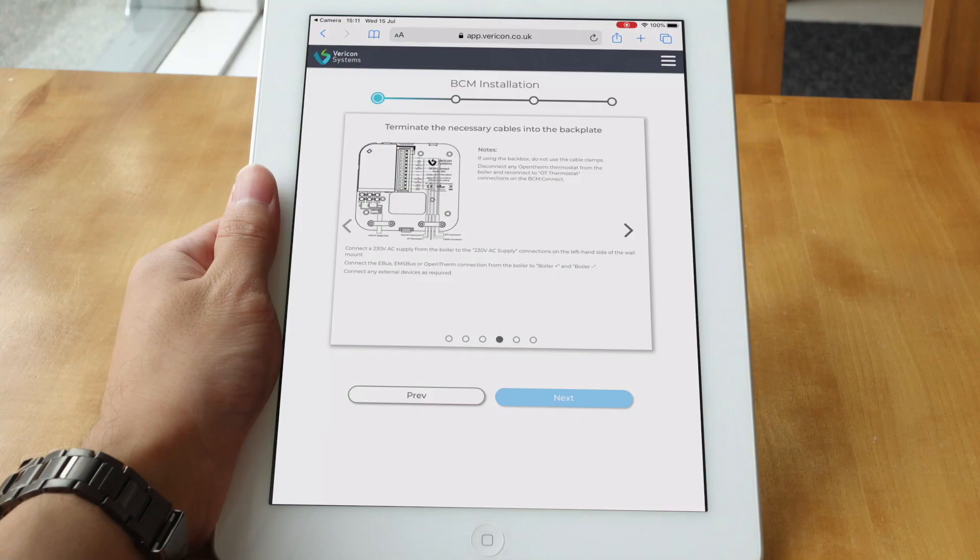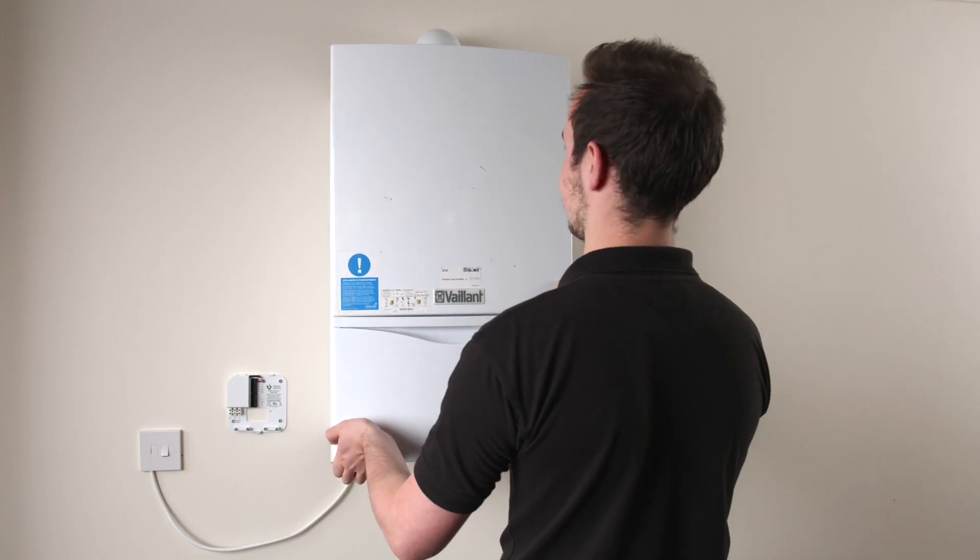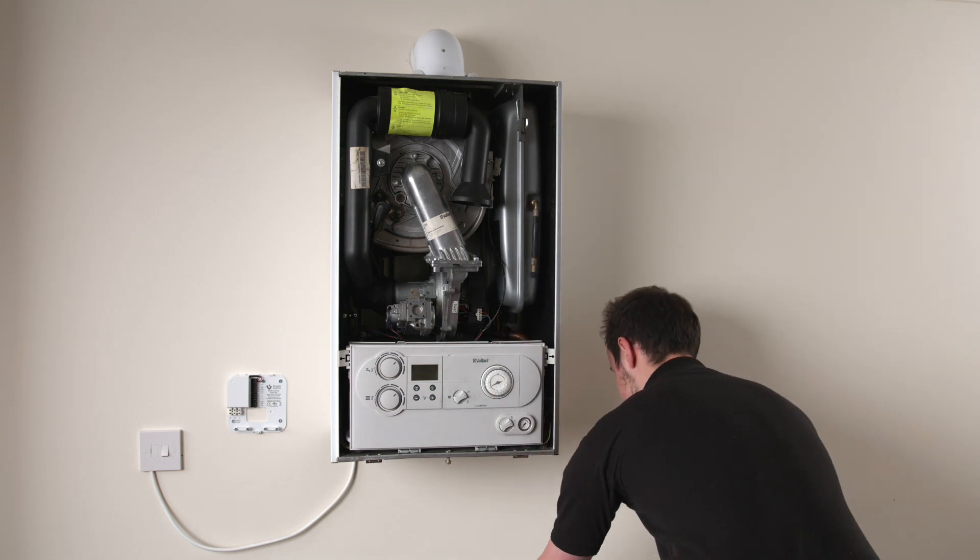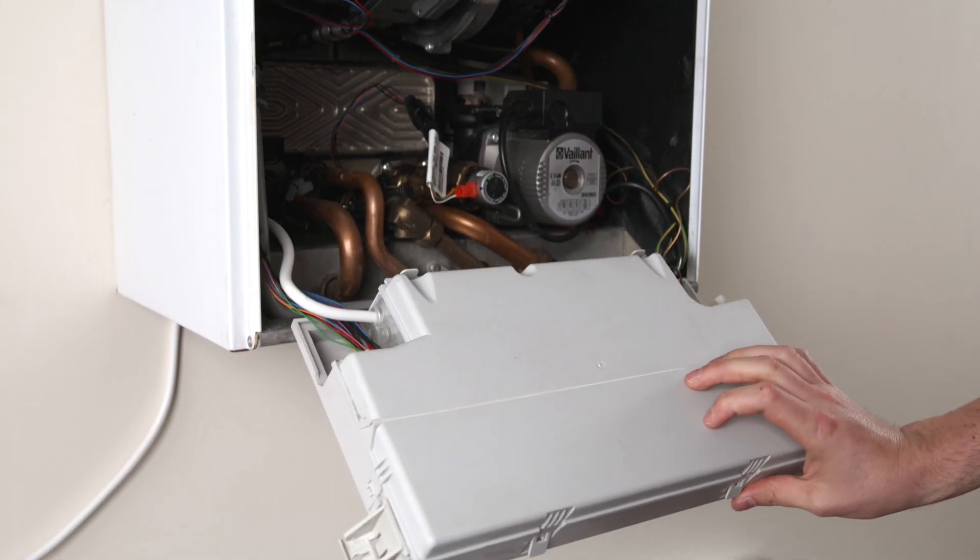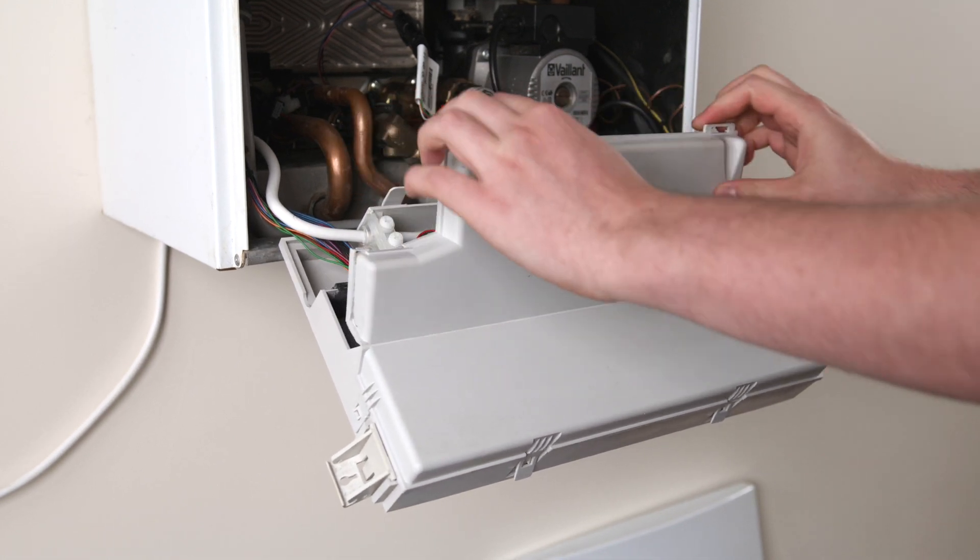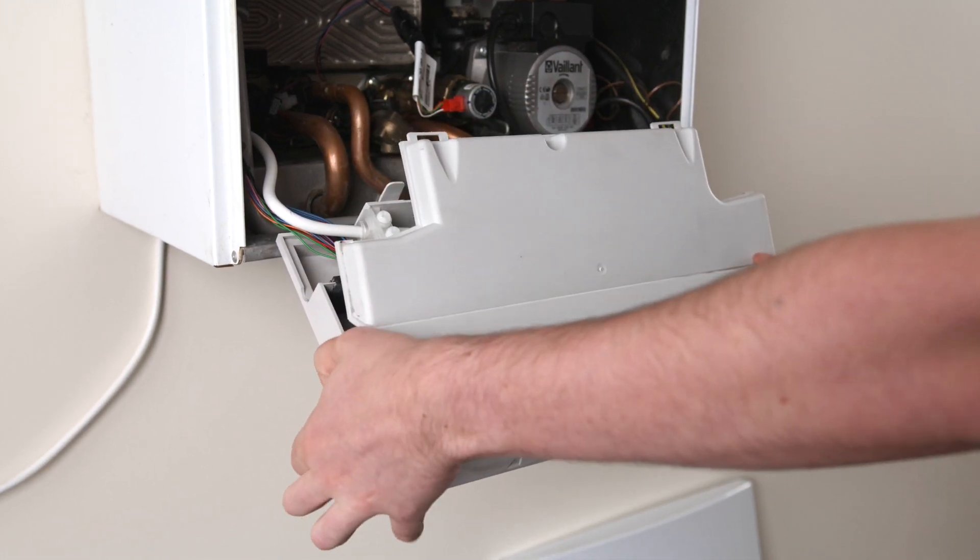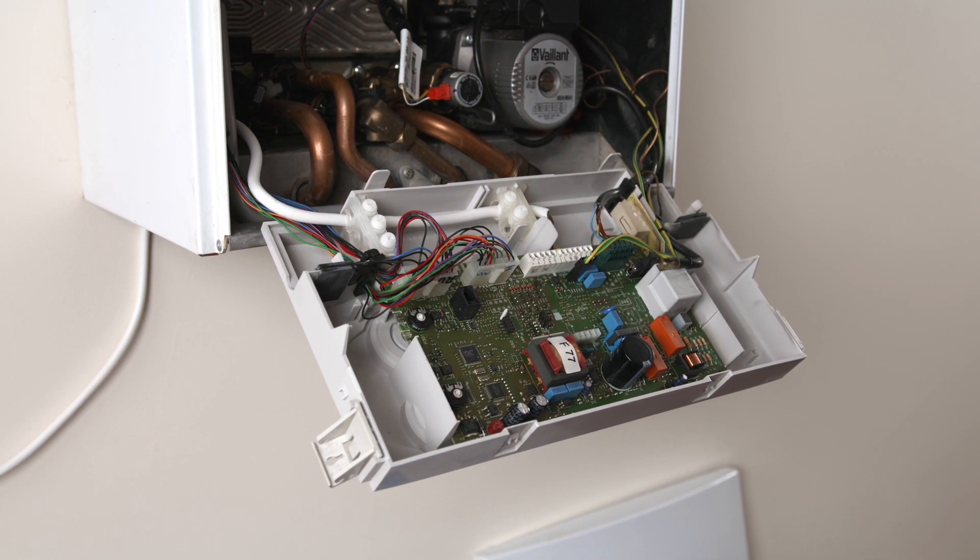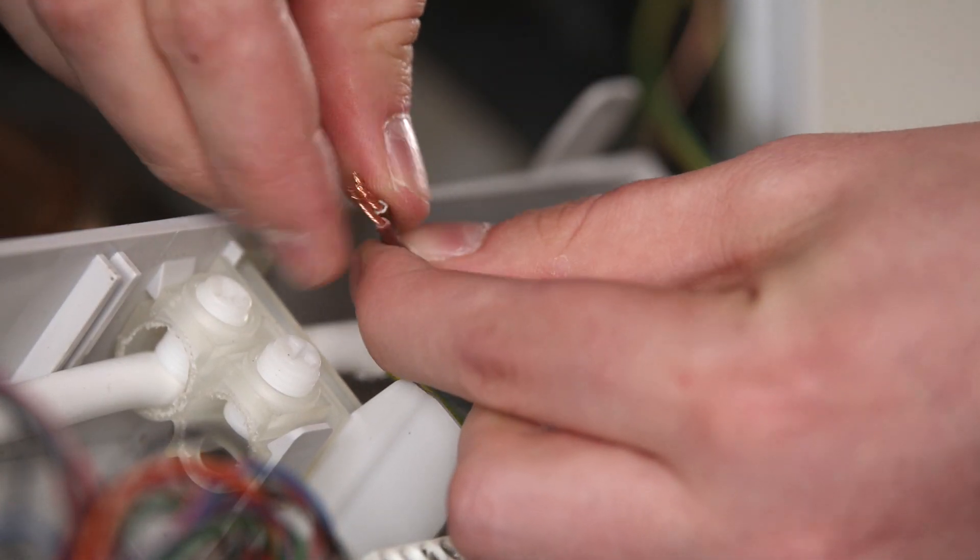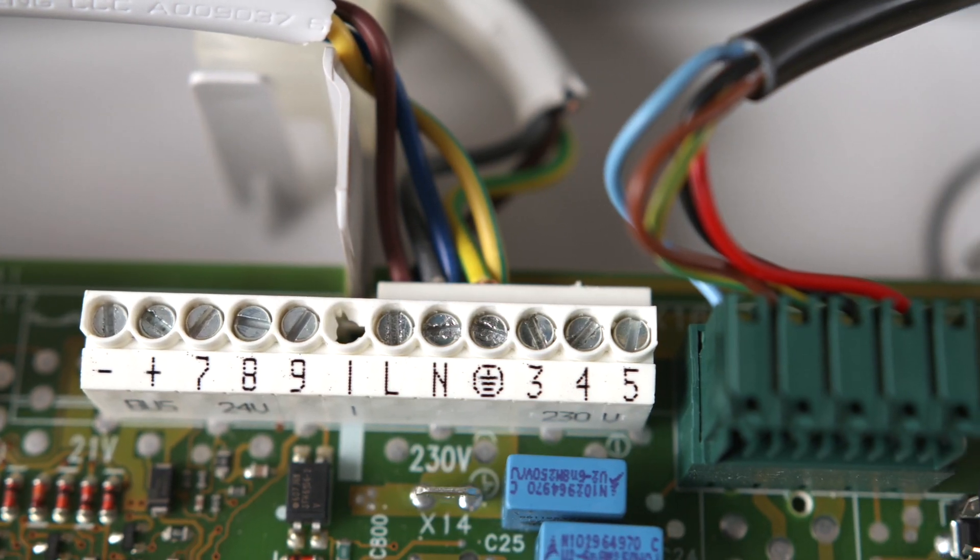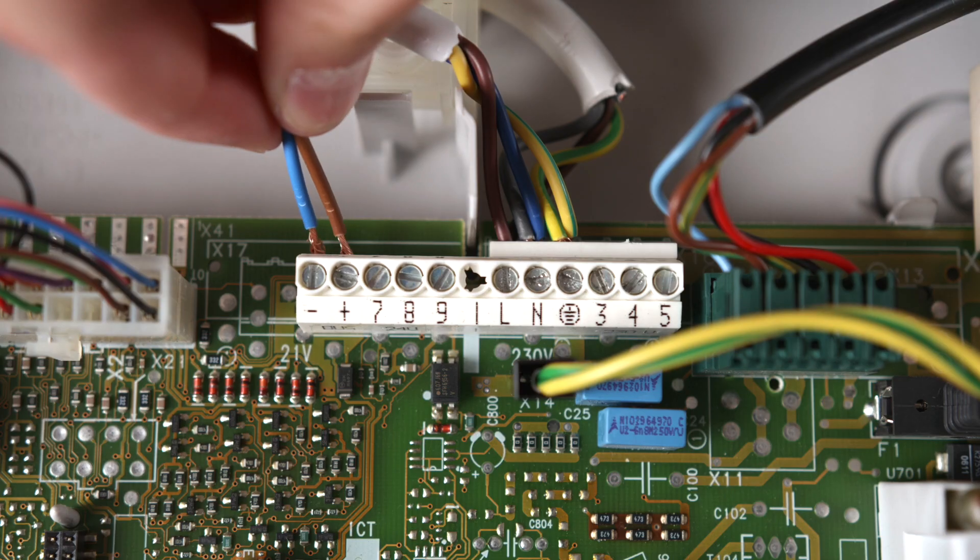Next, we will terminate the boiler bus cable and the 230 volt mains cable on the boiler side. To do this, remove the covers to access the boiler PCB. Any link or existing OpenTherm thermostat should be removed from the boiler bus connector before connecting the cable. If you have an eBus or EMS bus thermostat, it should remain connected. The BCM should be connected to the same supply as the boiler. This could be wired into the boiler's 230 volt connections or the fused spur.